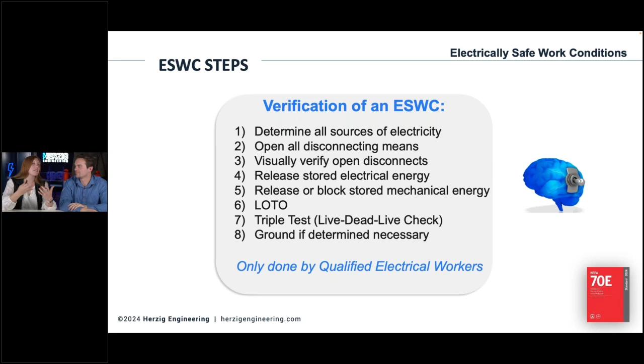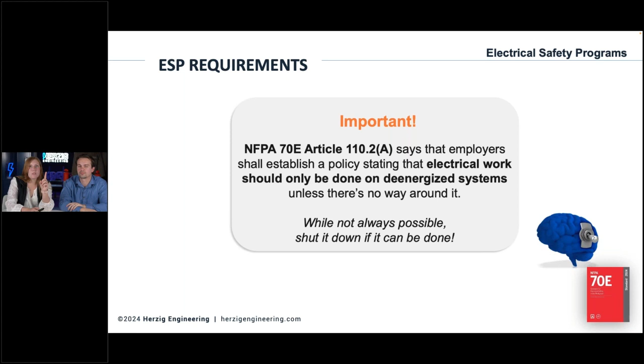Okay. Another note, Article 110.2A says that employers must establish a policy that energized work is last resort. Okay. Electrical work should only be done on de-energized systems. If it's not possible to do that, fine, you go through the whole energized work permit process, but be very careful with that, because if you don't have proper justification, and there are some examples of what would be considered proper justification for energized work, if you don't have that, you're directly violating even OSHA, all right? You should not be doing energized work unless you have true justification to do so, because energized work is the #1. Servicing, adjusting, maintaining any electrical equipment, 50 volts and above is the cutoff. Energized work is the #1 thing that kills people in the workplace whenever it comes to electricity. So don't do that unless it's justified. All right.